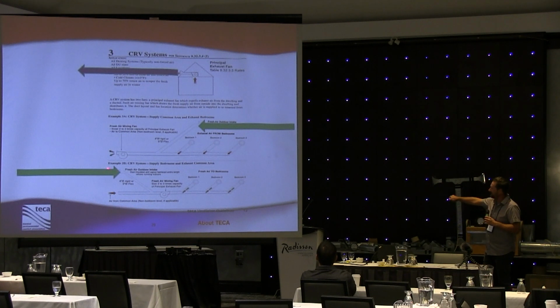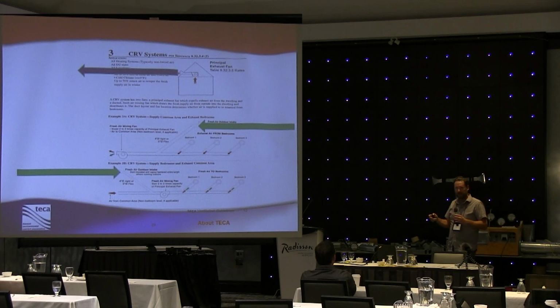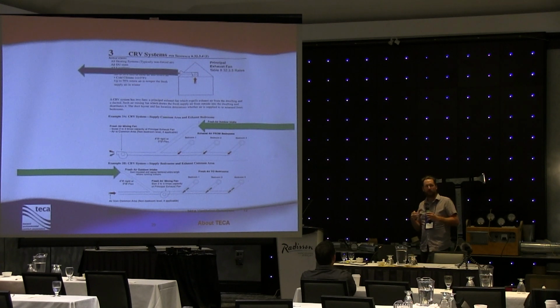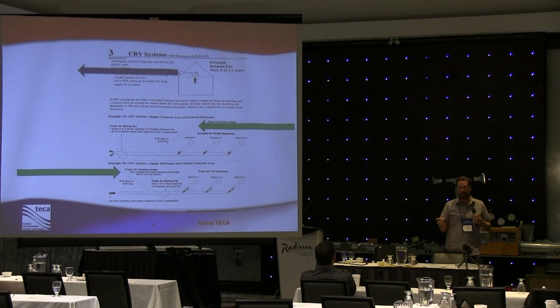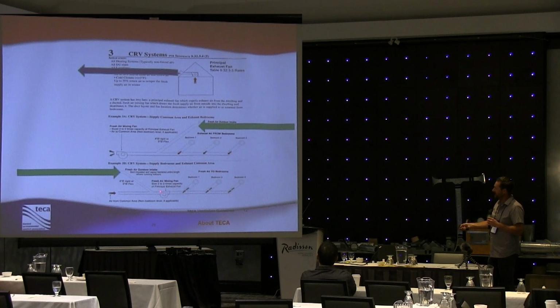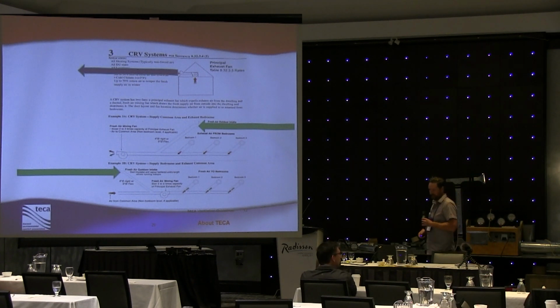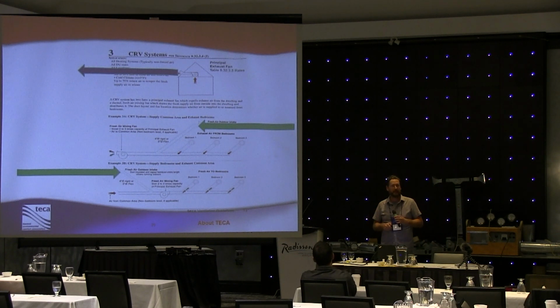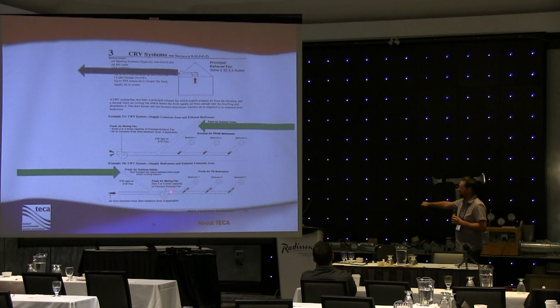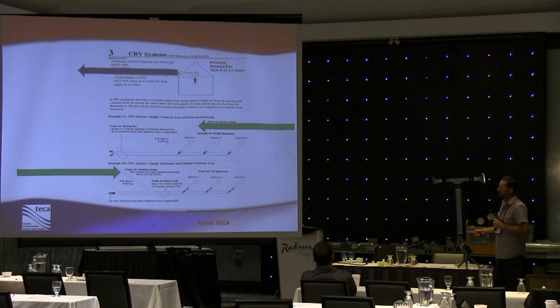Basically, the way this works is that we prescribe the size of the ductwork that has to bring the fresh air in from outside. You can use 4-inch rigid duct to bring the fresh air in from outside, or 5-inch flexible duct. Of course, since it's carrying unconditioned air, it needs to be insulated correctly so we don't have a sweat problem. But that duct that comes in, we have figured that with the connection to the back of this fan, this fresh air duct can be connected anywhere to this ductwork, and it makes very little difference to the volume of fresh air versus stale air that we're getting. However, absolutely, the longer the ductwork from the fresh air mixing fan to the first connection, the better the mixture is going to be, for sure. Definitely, it's a good question. Does that answer it, though?